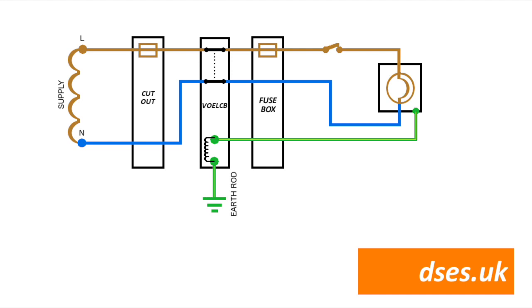And you can see that the earth passes back through the main earthing terminal in the fuse box and to the coil of the VOELCB via the F or frame terminal. On the other side of the coil is the E terminal we saw earlier, which connects to earth via the rod.